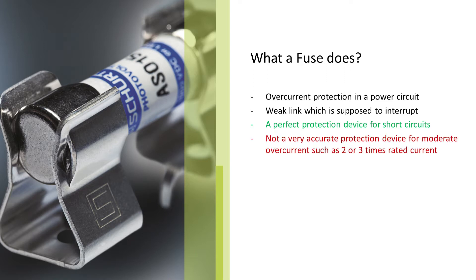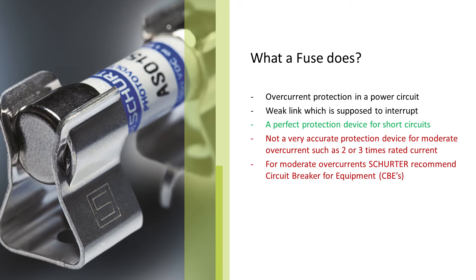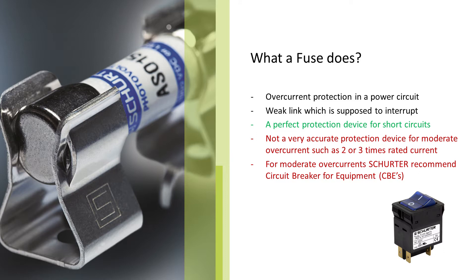However, it is not a very accurate protection device for moderate overcurrents such as 2 or 3 times rated current — what we would typically experience with a power overload of an electrical motor. For such moderate overcurrents, Schurter recommends using a circuit breaker for equipment, also known as a CBE.